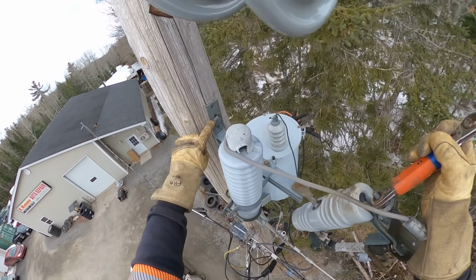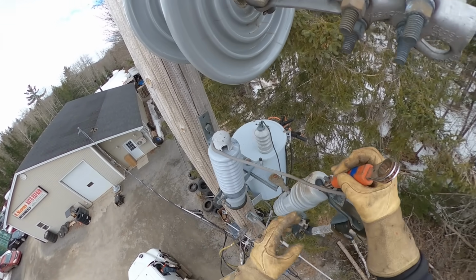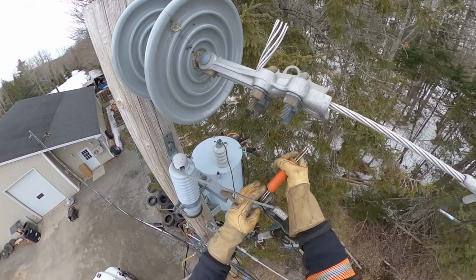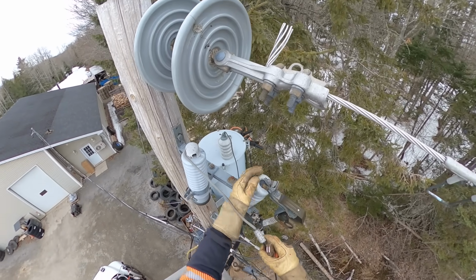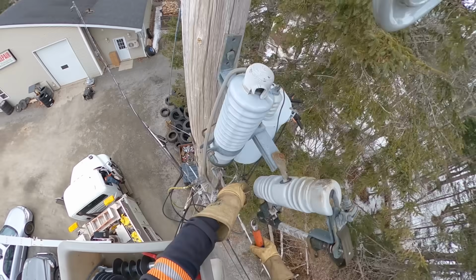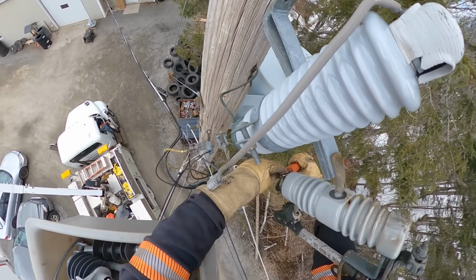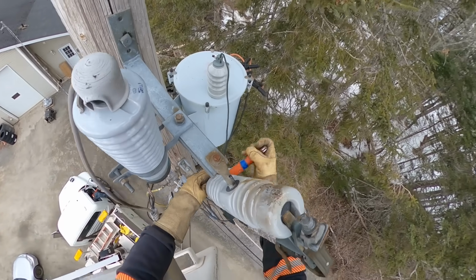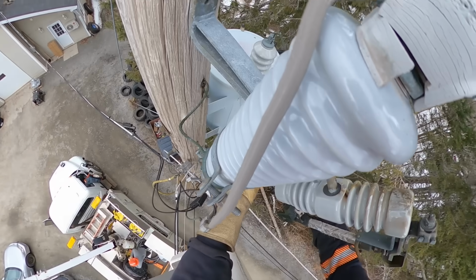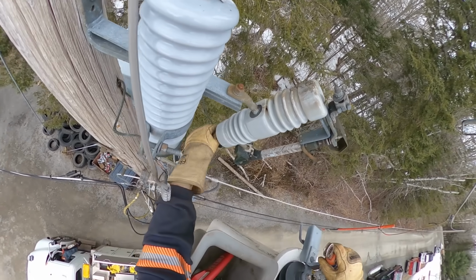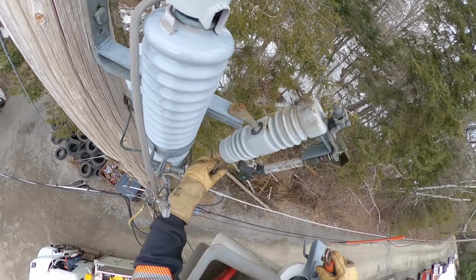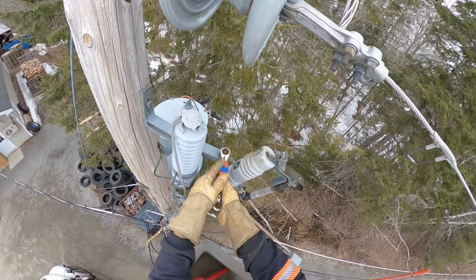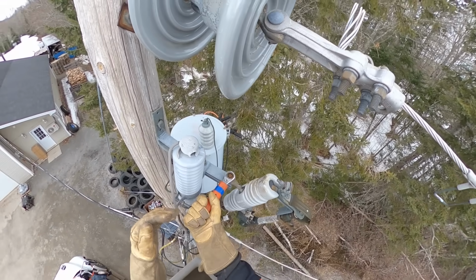And I'm just noticing there's some arcing on the bolt and the pole is what I was pointing to. So either the fault current when the squirrel was standing on the steel traveled through him for a moment and in towards the pole, or there could be some hairline cracks in that cutout as well. I don't see any cracks in the cutout though. You can see all these bolts are all pretty rusty. We're gonna change that all out.